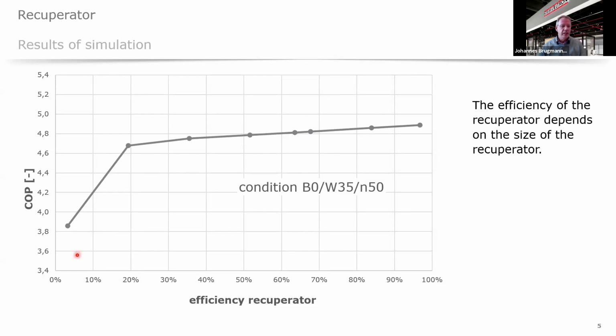And what you can see here is that you can increase the efficiency of the unit from 3.8, for example, to more than 4.8 at these special conditions, if you move the evaporation for the superheat into the recuperator, and if you don't, you lose this efficiency, and that is the most important point if you want to use R454C as a refrigerant.